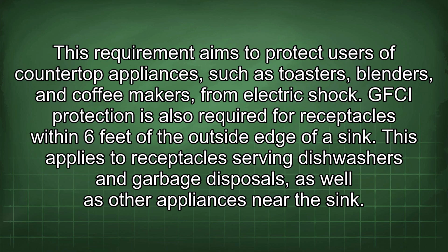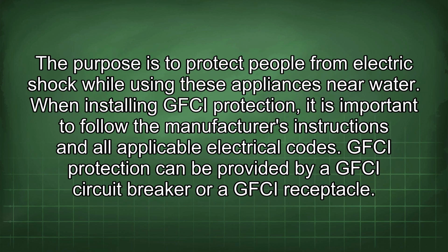GFCI protection is also required for receptacles within 6 feet of the outside edge of a sink. This applies to receptacles serving dishwashers and garbage disposals, as well as other appliances near the sink. The purpose is to protect people from electric shock while using these appliances near water. When installing GFCI protection, it is important to follow the manufacturer's instructions and all applicable electrical codes. GFCI protection can be provided by a GFCI circuit breaker or a GFCI receptacle.